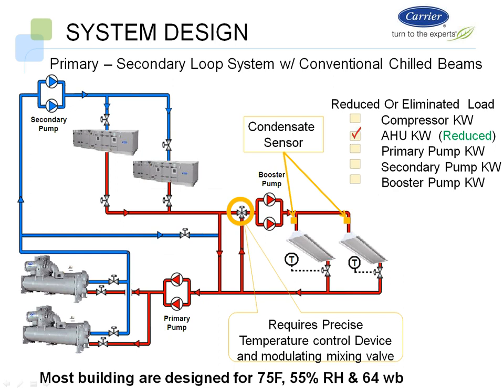So then when you look at a system design with a conventional type chilled beam application, you start getting some more benefits, even with the traditional beams, of your chillers, your air handlers, and then your chilled beams. The only difference here is with your primary secondary loop, you also have to add some more control complication, as well as some piping complication, because you typically now have to install a three-way valve to bypass that water back to the beams, because if the water is too cold going out there, you have to make sure it's heated up. So a lot of times the systems will either have this three-way valve in there, sometimes even a plate heat exchanger, or even a boiler induced into that piping system to make sure that water temperature stays above the ambient dew point. So it puts a little complication in there.